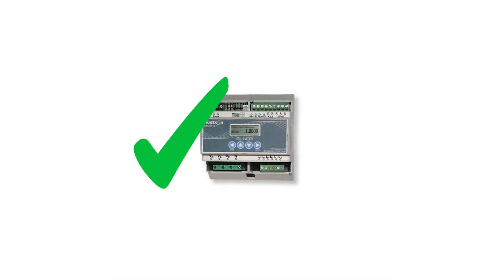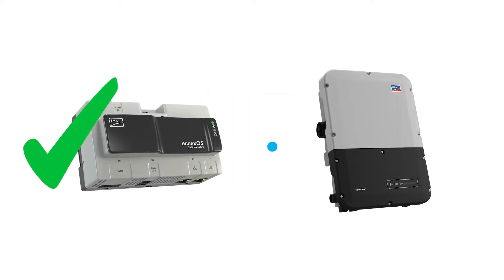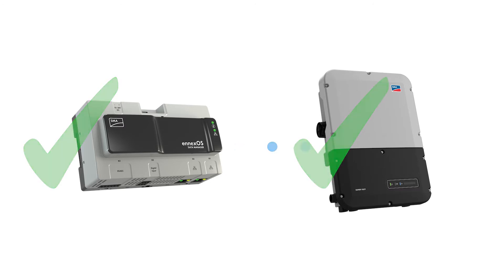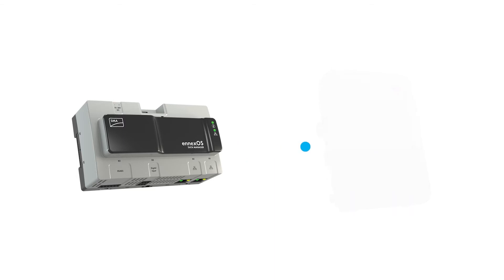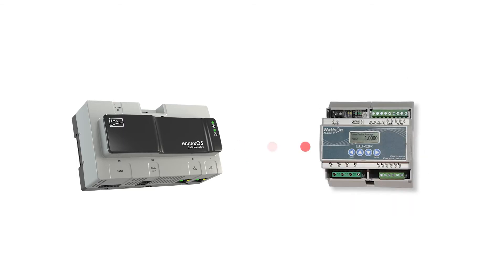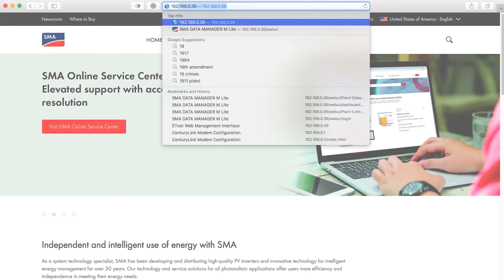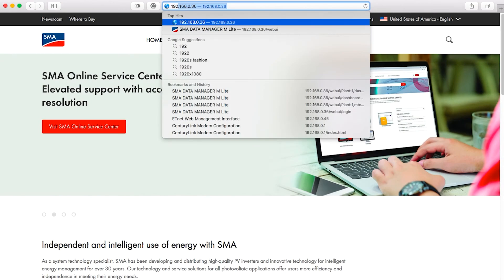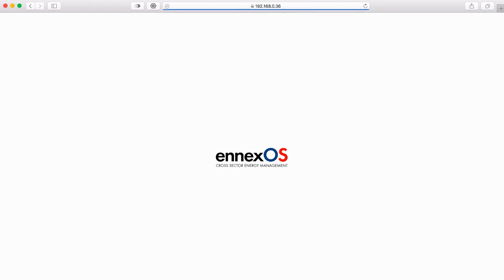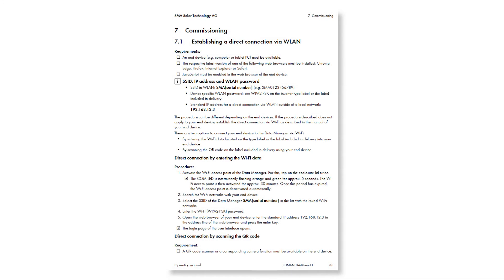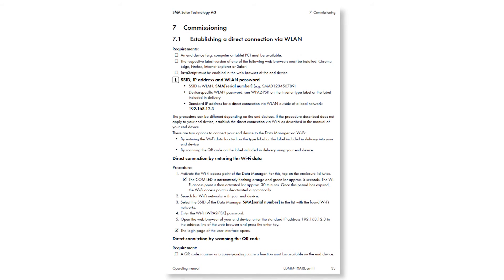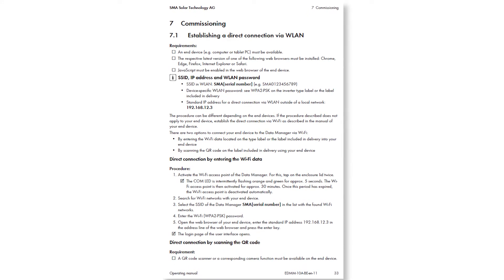Now the energy meter is fully commissioned and ready to be configured for use by the data manager. In this example, we have already commissioned the Data Manager M Lite and the associated Sunny Boy inverter. So we will demonstrate adding the meter to a commissioned data manager. The meter can also be associated with the data manager during that device's original commissioning. The energy meter is linked to the data manager through the user interface of the data manager. We will demonstrate accessing the user interface on a computer with a wired LAN connection using the IP address assigned to the data manager. Please consult the Data Manager M Lite operating manual section 7 for other options to access the user interface.